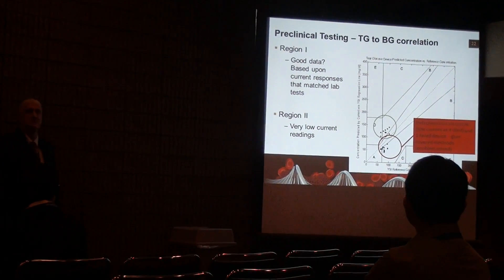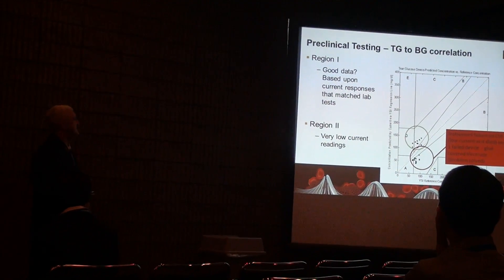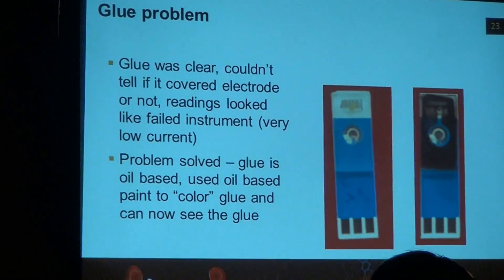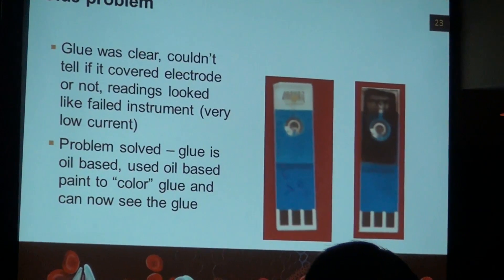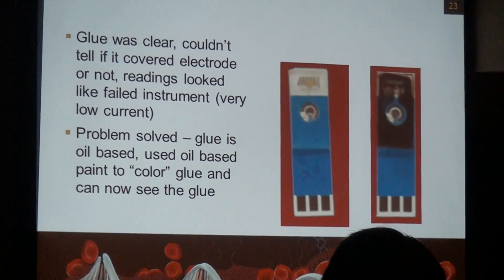As far as correlation to blood glucose, we were a little frightened because when we got our initial Clarke error grid, we quickly found two populations of data. What ended up happening — and I can say this now — I was so lucky that I had a device fail on me with one day left on the warranty, so I could get it repaired. We also had a manufacturing issue that was quickly fixed by adding oil-based paint to our clear glue so we could actually see where we were gluing, because the problem was we were closing off the channel on some devices and covering up the electrodes on others, giving very low current. We couldn't figure out what the problem was until we took that step.